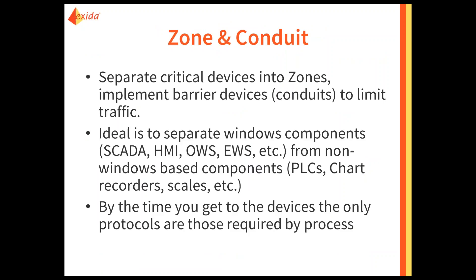As part of the 62443 standards, one of the major steps is to separate the critical devices into zones and implement some sort of a barrier device — generally referred to as a conduit — to limit the traffic that gets to those end devices. The ideal solution is to separate your Windows components like your SCADA systems, HMIs, and embedded CE devices from your non-Windows-based components like PLCs, chart recorders, and scales. The reason is that a Windows device can be compromised by a virus. If infected, it will probably not directly infect the PLCs, but what happens to the network due to that infection can cause unwanted or even catastrophic results.